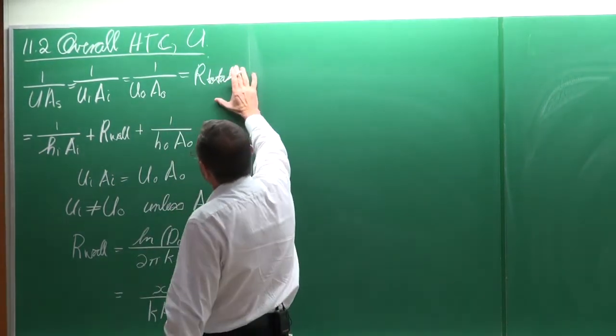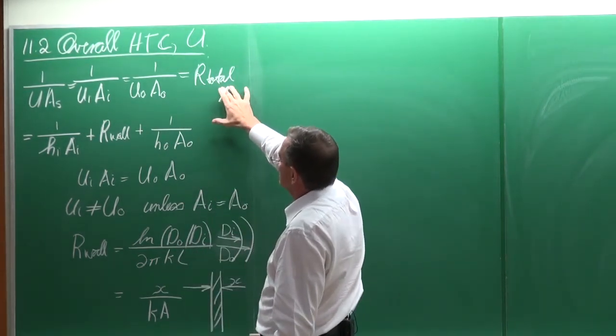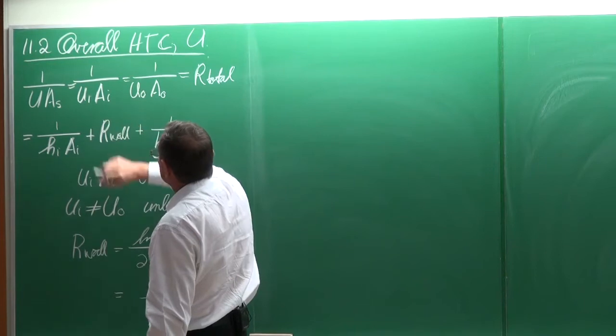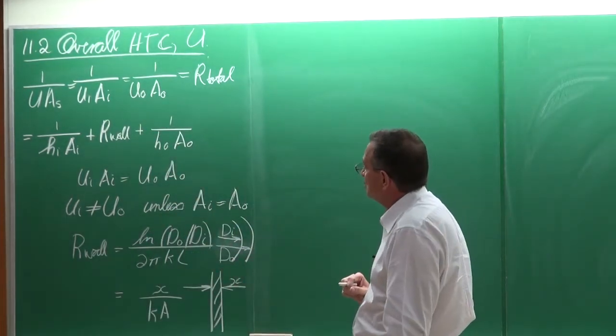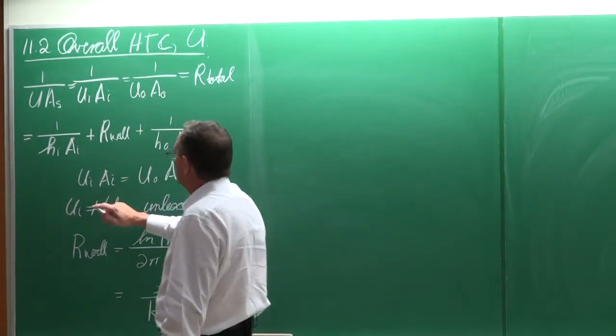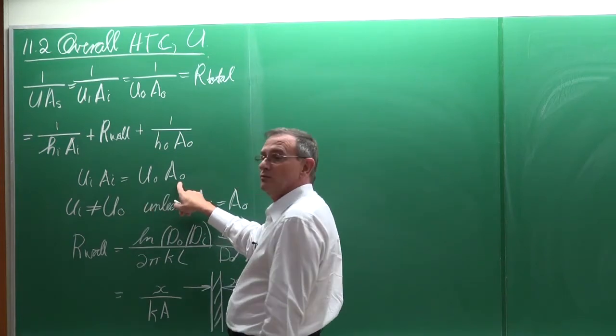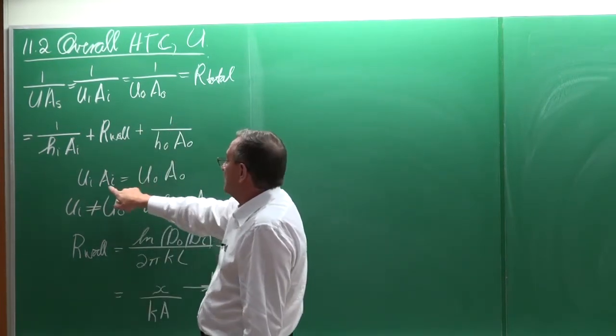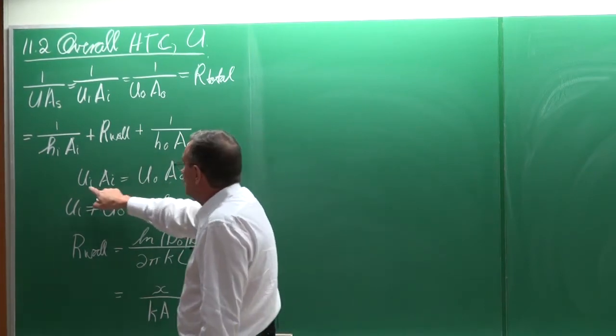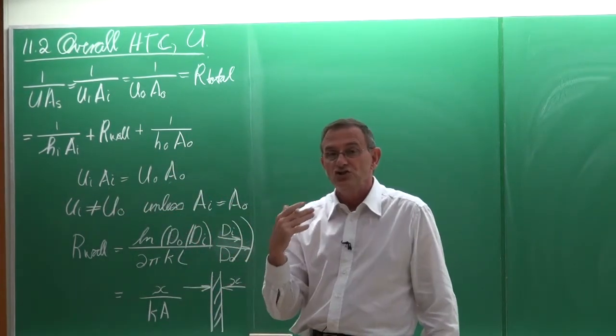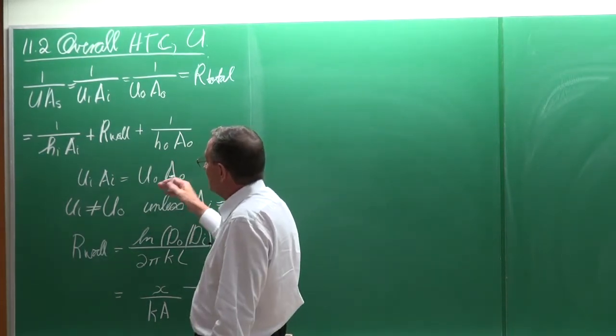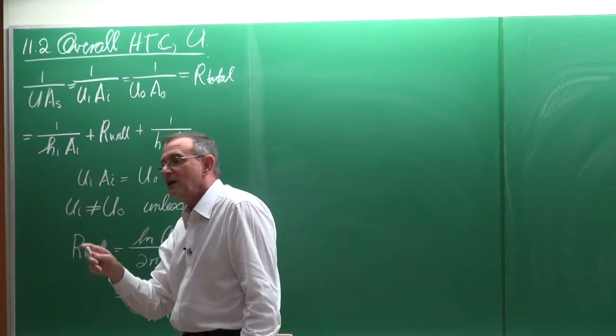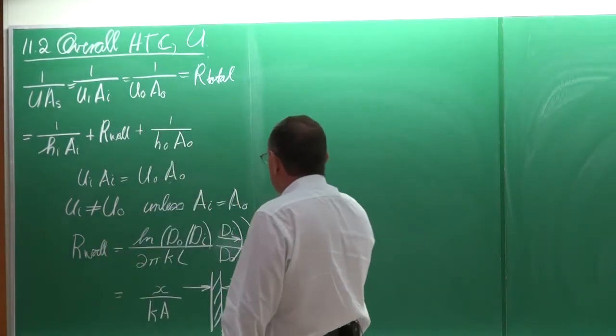In terms of deriving U, it comes from the total resistance. The resistance can be written as the resistance of the inside heat transfer coefficient, the resistance of the wall, and the resistance of the outside heat transfer coefficient. In general, U multiplied by the area on the inside equals U multiplied by the area on the outside. Normally these two are not the same, except when the areas are equal. It's very important to always ask whether U is based on the inside or outside area.